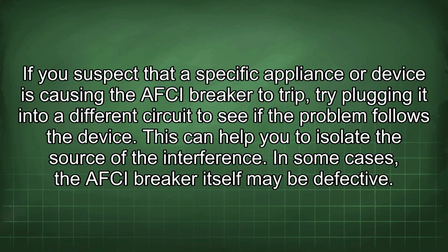If you suspect that a specific appliance or device is causing the AFCI breaker to trip, try plugging it into a different circuit to see if the problem follows the device. This can help you to isolate the source of the interference. In some cases, the AFCI breaker itself may be defective.